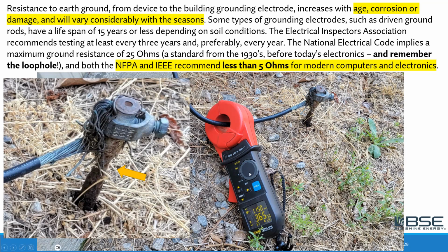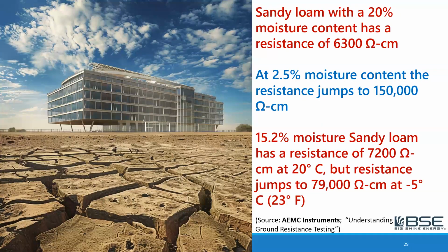And if we look at our AEMC clamp meter, we can see that we're getting a very high resistance, 365 ohms. So that's useless compared to a practical requirement to be less than 25 ohms. Even if it was allowed, if this was a redundant or second grounding electrode at this building, it's doing nothing for you. So one of the things that AEMC Instruments, which makes the meter that you just saw and makes many other types of grounding meters and power quality meters, they are experts in grounding, and they do a lot of training in how to do grounding assessments.